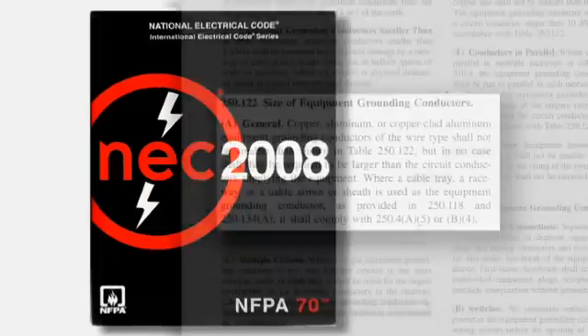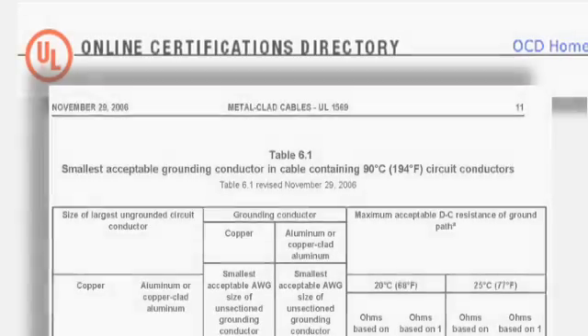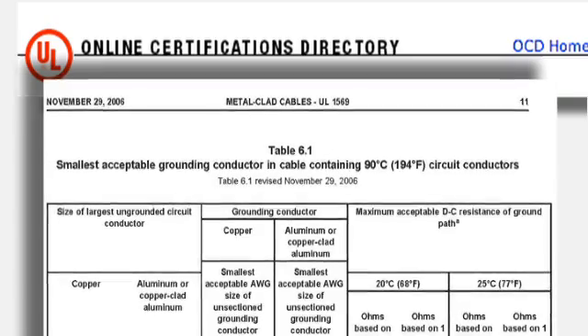A common misconception is that a green copper ground performs better than the armor of MCAP cable. The answer can be found in Section 250.122 of the National Electrical Code and Table 6.1 in the UL1569 MC Cable Standard. Both MCAP cable and traditional interlocked armor MC cable are types of MC cable. The only difference is in the ground path. A copper ground, an aluminum ground, or an armor ground all must meet the same UL and NEC ground path performance requirements.